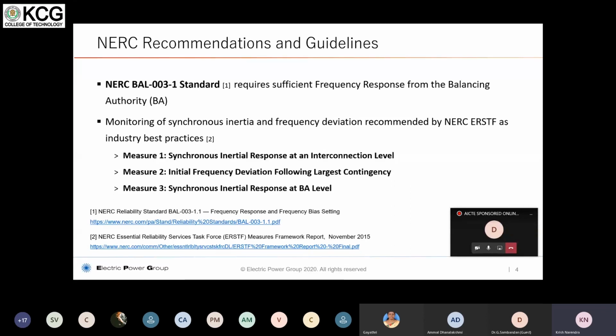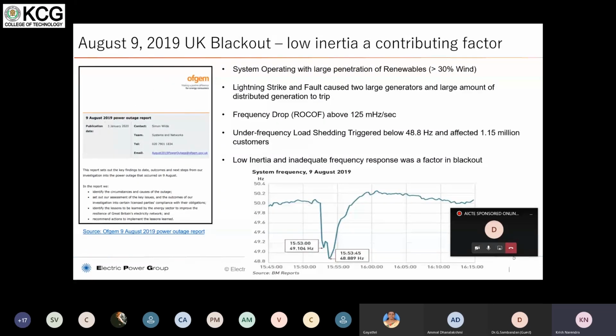Let us see, in reality, how this has happened in a recent blackout, the August 9th, 2019 UK blackout. Now, even though inadequate inertia was one of the major contributing factors, the reason this blackout started was a lightning strike at two big generators. Approximately, the combined generation was around 2000 megawatts.